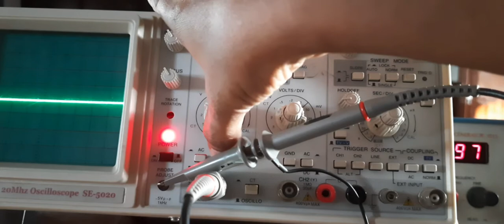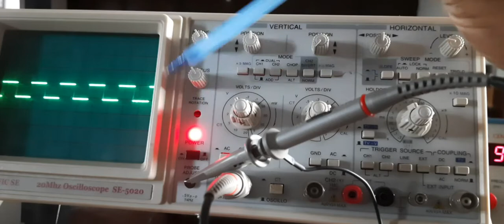And now I am measuring an AC. So I will release this ground and put it in AC. Now I have connected this calibration signal from the CRO to calibrate the CRO itself. So let's measure the voltage. In fact, you can see this is a square wave, not a sine wave. If I ground it, the reference zero line is this. So if I release it, you can see it's 1 division height.